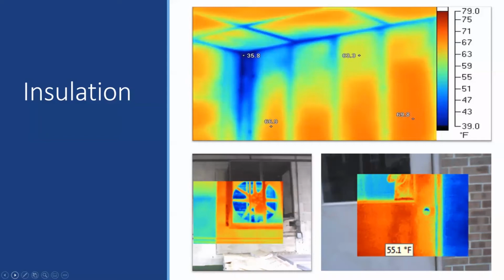Note for all three of these pictures, hot and cold are determined by the infrared camera, and in this case, all three pictures refer to red as being near 80 degrees Fahrenheit, and the blue-black as referring to 39 degrees Fahrenheit. We can see the cool air from the outside is leaking into a room from an exposed vent fan. And in the top photo, you can see that the corner of the room is missing insulation or has damaged insulation. You would need to investigate further to find the root cause, but you did discover an issue and therefore know you can correct it.